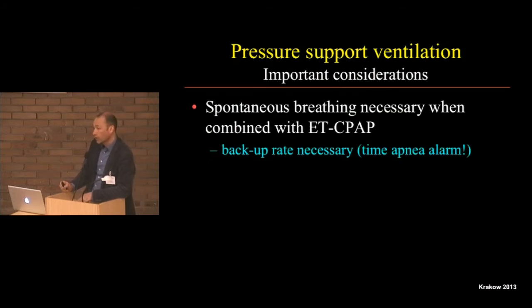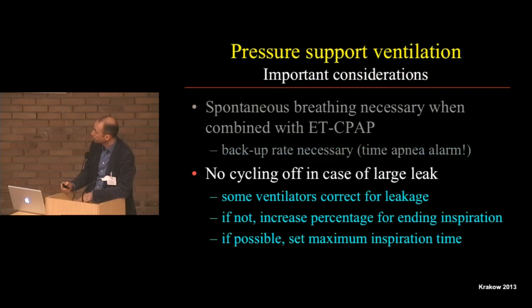It's important to realize that for pressure support ventilation, you need spontaneous breathing, especially if you combine it with endotracheal CPAP. This means that, especially in our preterm babies, you need a backup rate. So in case the baby does not spontaneously breathe, the machine should sense this and start a sort of backup ventilation until the baby starts breathing again.